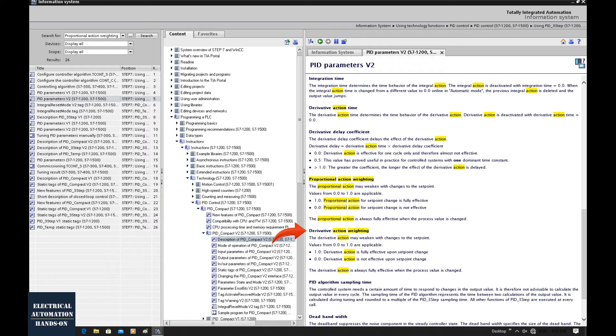For the derivative action weighting, the idea is similar — you can read the detailed description. If it equals 0, the derivative action is not in effect upon a set point change. Most of the time, we prefer to set 0 or 0.1 on the derivative action weighting. If the set point changes too much in a short time, the output would give a very high value. To prevent this, we prefer to set 0 so the derivative action is not effective on set point changes, since in most control systems we want the PID controller to work against disturbances.